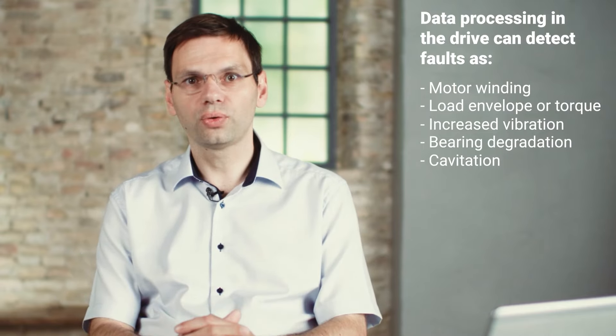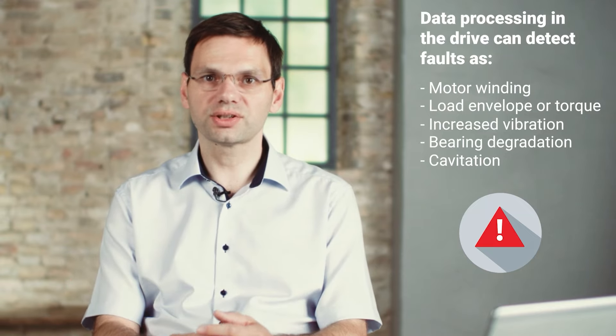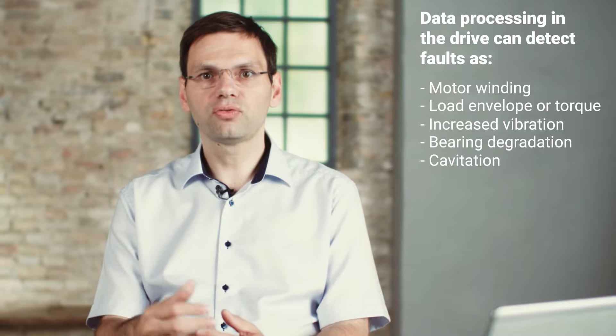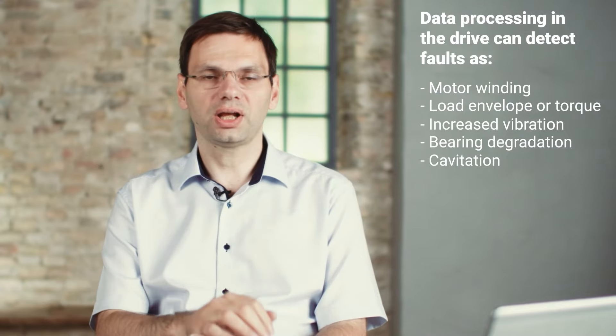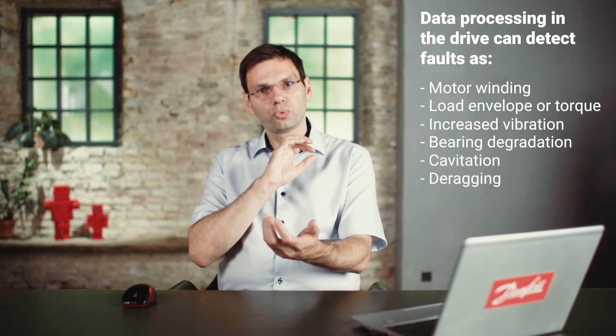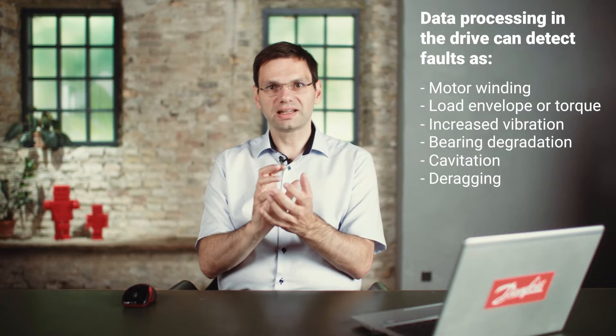When the drive detects a fault, it can notify the user so that a maintenance technician can be sent to the installation to fix the problem. But the drive can also do something by itself about the fault, depending on what it is. For example, with a wastewater pump, if dirt clogs the pump and it cannot turn, a function called deragging makes the pump run briefly in reverse — forth and back — to clean the clog and free the pump, which can then resume normal operation.